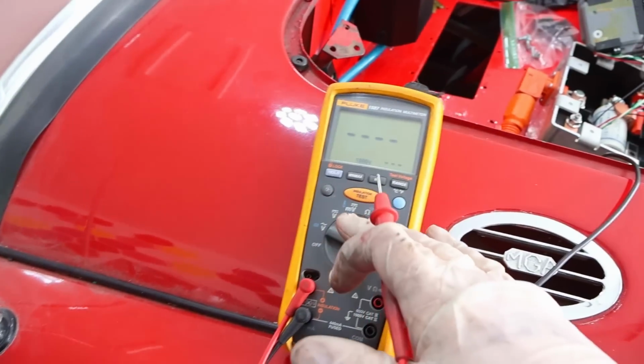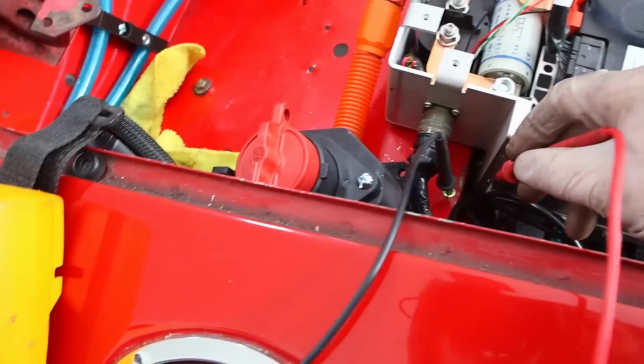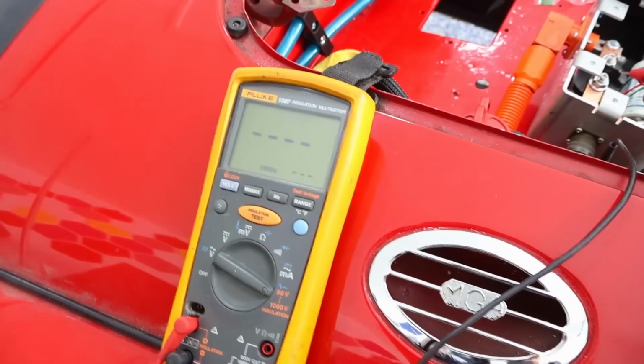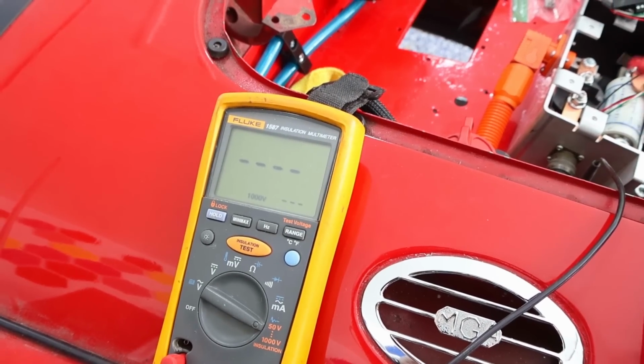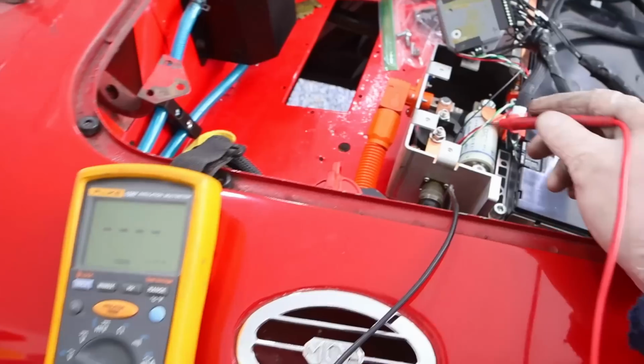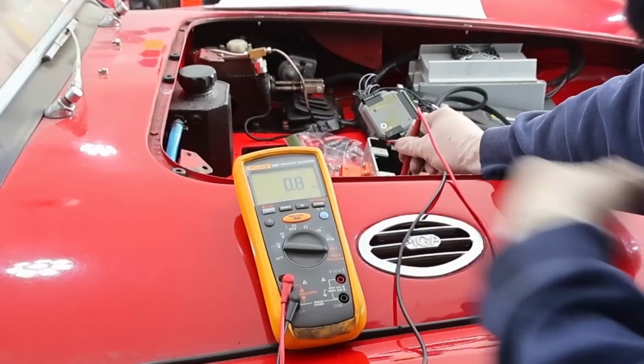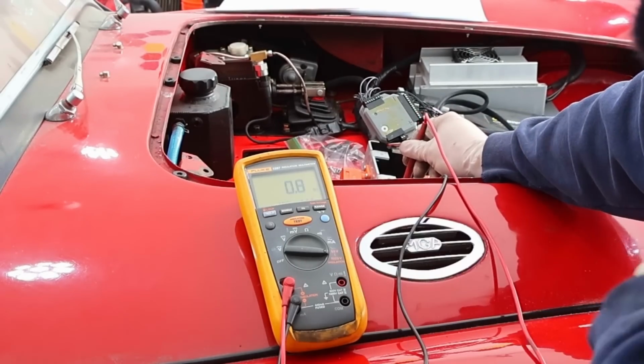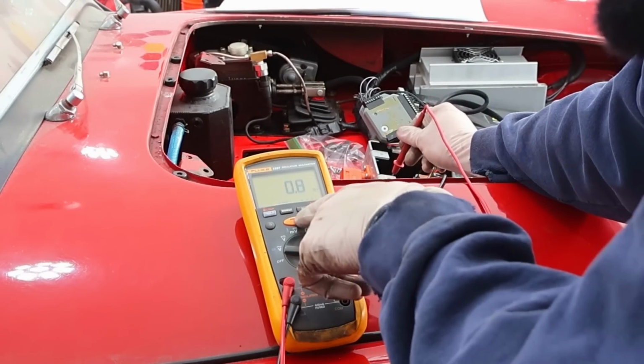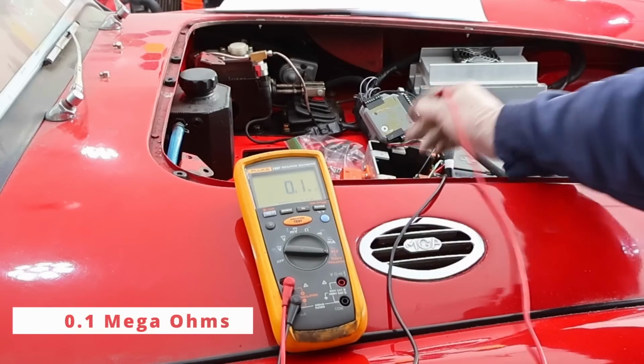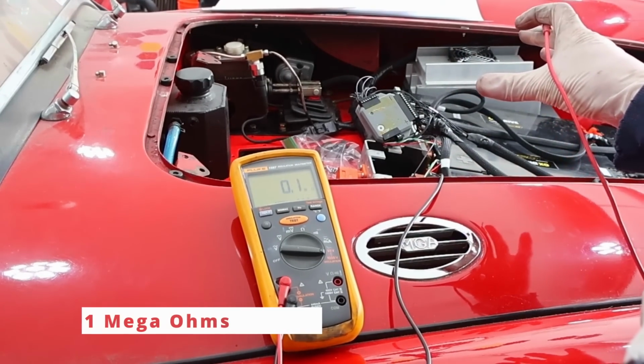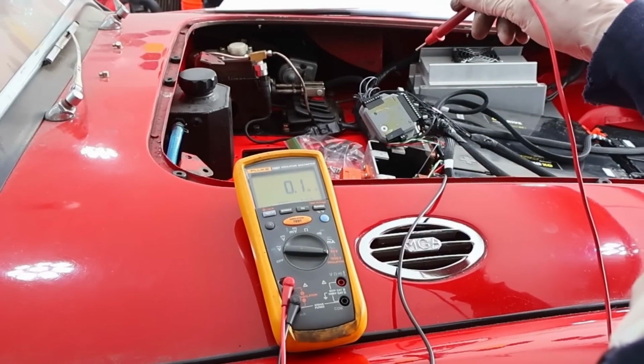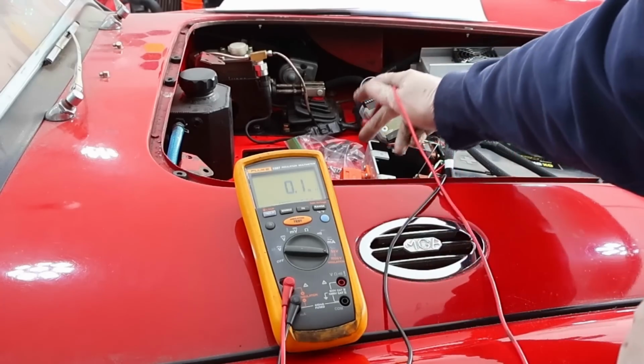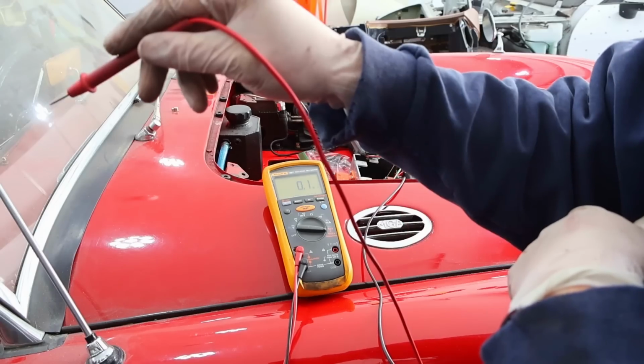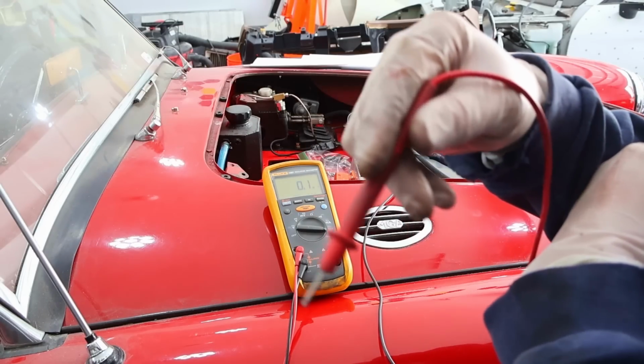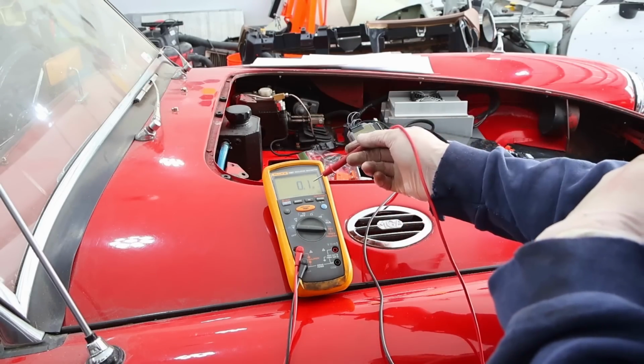This is my loss of isolation meter. I've got it connected to a part of the chassis, and I'm testing before the contactor as well as after the contactor. Before the contactor: 0.8 giga ohms, really good resistance. After the contactor: 0.1. So the battery box itself is very isolated, but somewhere between this connection and the wiring, including the high voltage junction box, we've got not very good resistance.